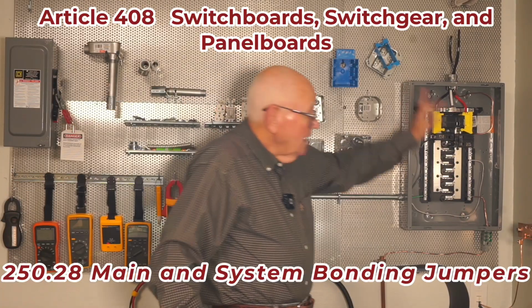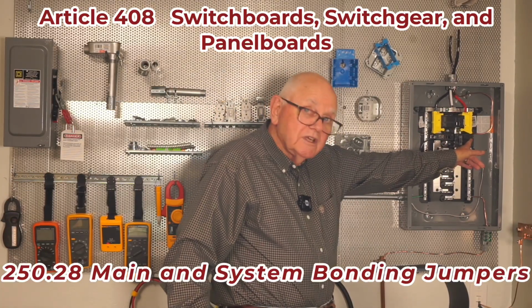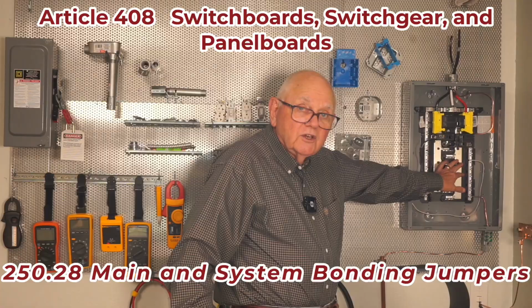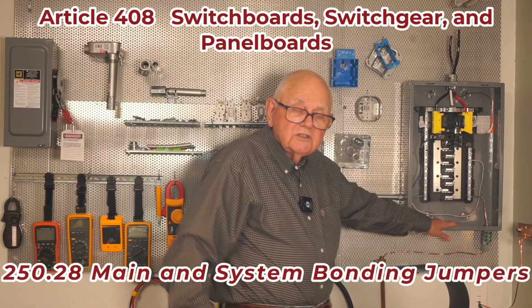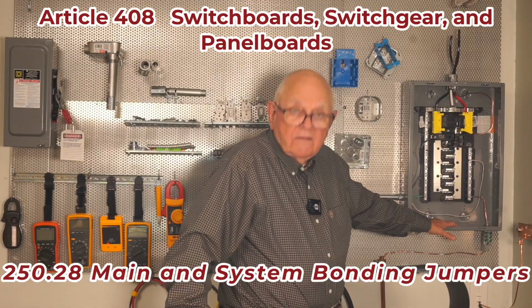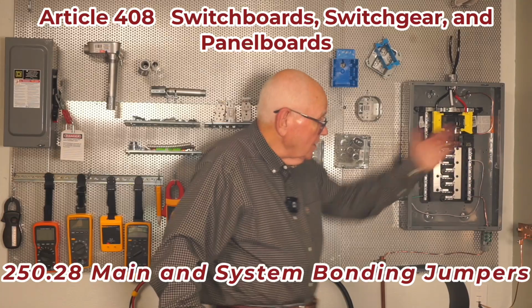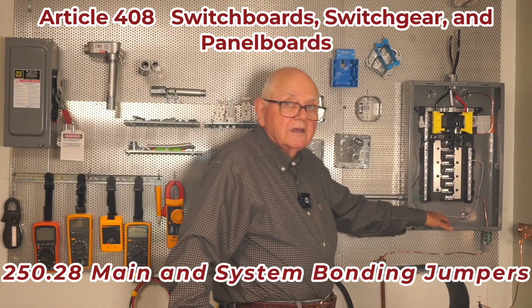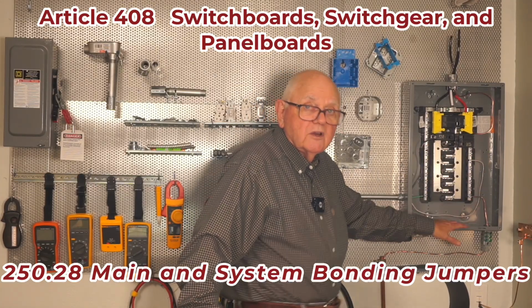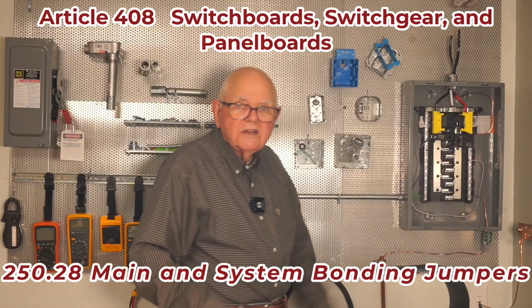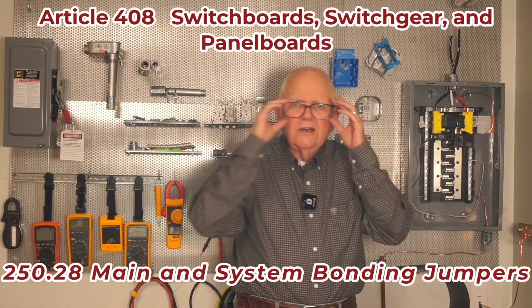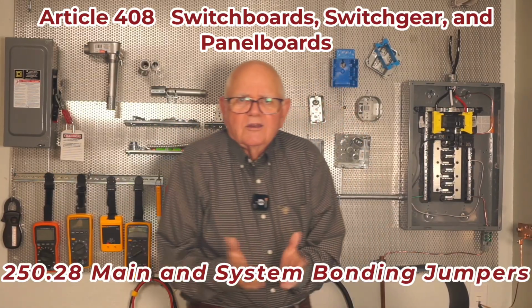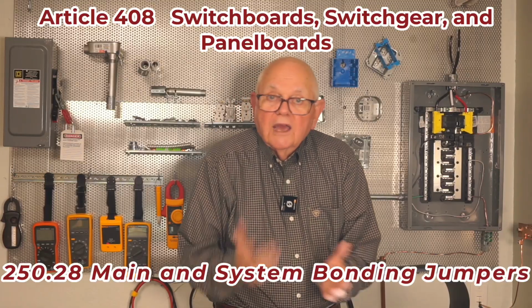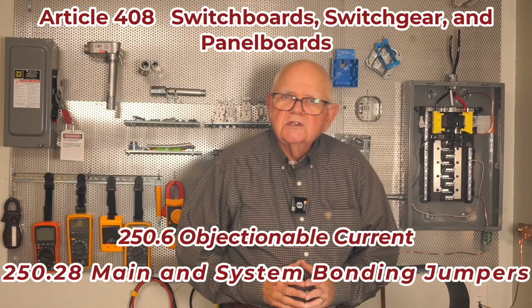If I screw that green screw into the panel and connect the neutral bus bar to the metal frame of my equipment, there's a path for current flow. Current returning on my neutrals from my loads can now flow into the metal frame of the equipment, through the equipment grounding conductors and back to the main panel. I don't want that to be a normal current-carrying path for current flow. That's a violation of 250.6.